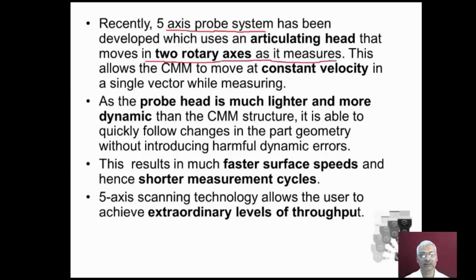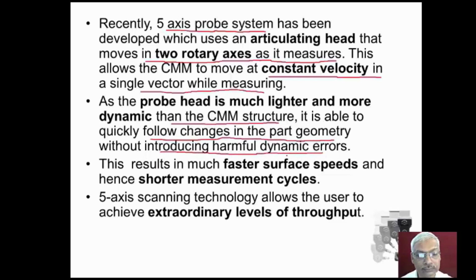5-axis probe system has additional two rotary axes, A axis and B axis, along with XYZ motion given by the CMM structure. This allows the CMM to move at constant velocity in a single vector while measuring. As the probe head is much lighter and more dynamic when compared to the CMM structure, it is possible to quickly follow changes in the part geometry without introducing harmful dynamic errors. This results in much faster surface speeds and hence shorter measurement cycles. 5-axis scanning technology allows the user to achieve extraordinary levels of throughput.